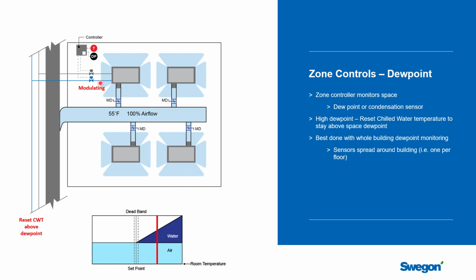The last one we'll talk about is resetting the chilled water. The problem with just closing the valve and saying you can't have any chilled water because we don't want it to sweat is that we've now lost complete temperature control of the space. And so any occupant in the space is going to be dissatisfied very quickly.